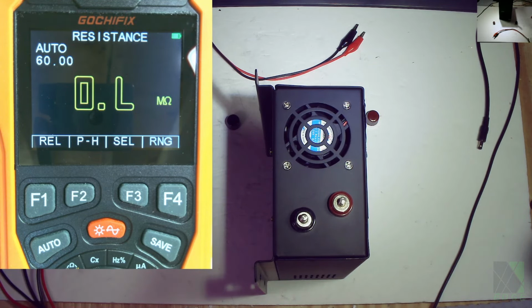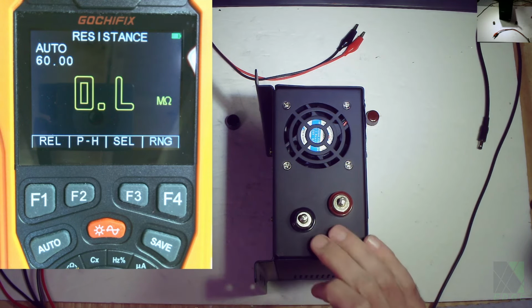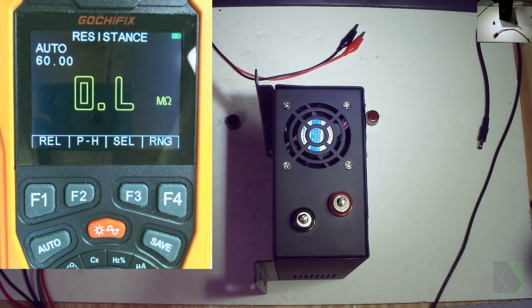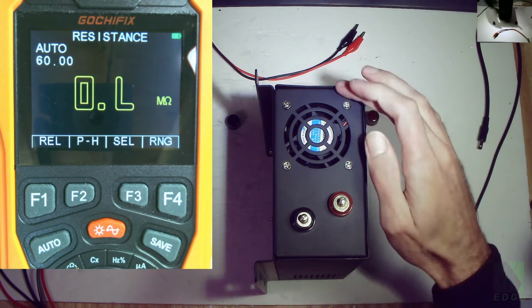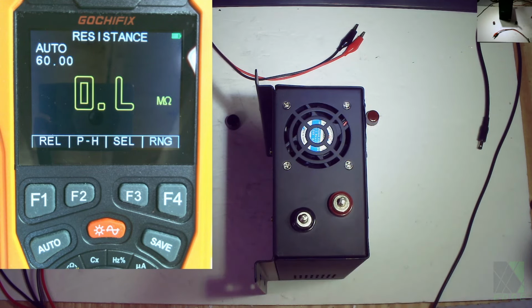But you can also determine one more piece of information, and that is, it's not a short circuit, but it's also not an open circuit. So this inverter most likely has the fuses intact. And most likely what we're seeing when we measure it is the input capacitors, which are across the input, and we're seeing the input resistance of the inverter is very, very high. And so that means there's really nothing wrong with the input of the inverter.